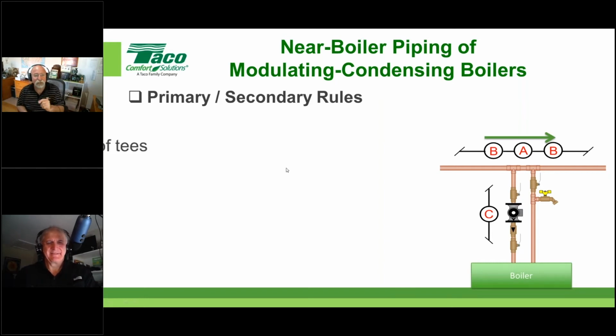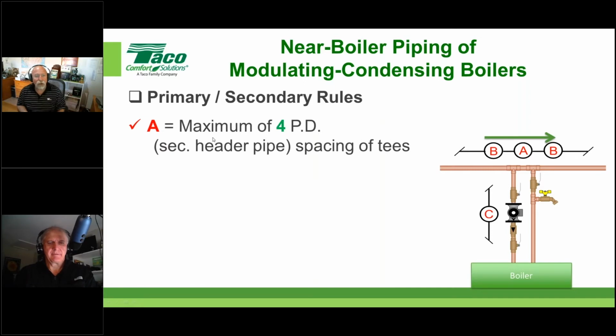Okay, primary, secondary rules. The rules are a maximum of 4 pipe diameters. Well, what are you talking about, Rick? We're talking about that A note. Look, I'm talking A here. We're talking A. And anytime you see the word maximum, it doesn't mean to take your tape measure out and measure and cut that piece of pipe that distance. We're saying try to get it closer than that. Okay, people misunderstand when we give words like maximum and minimum, so I always want to point that out.